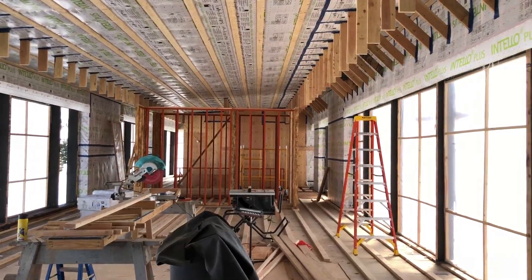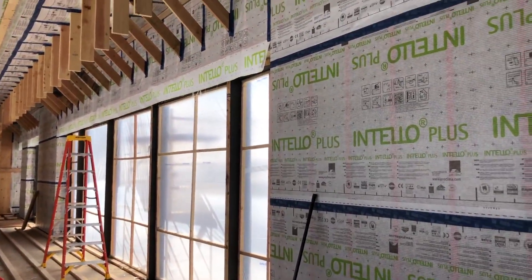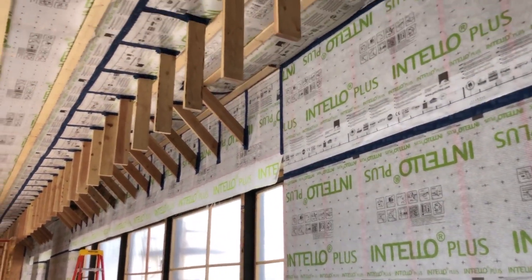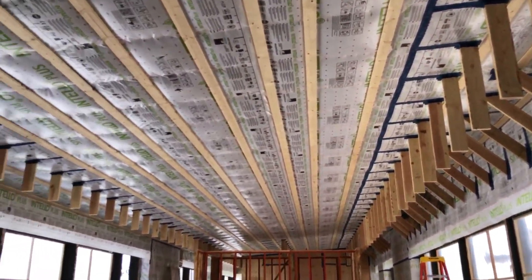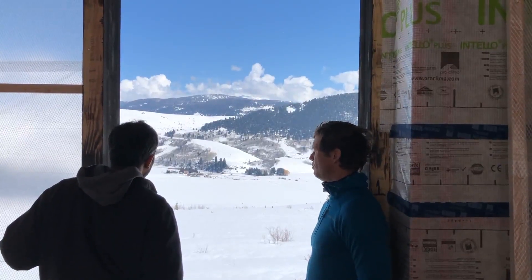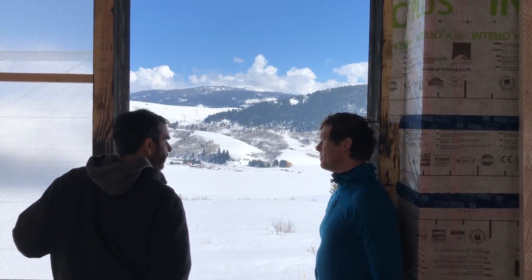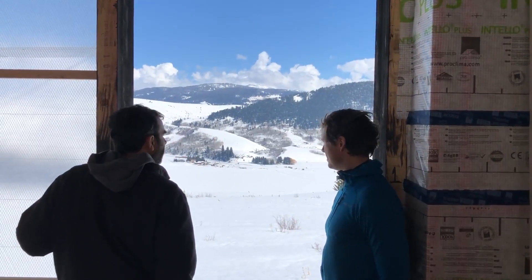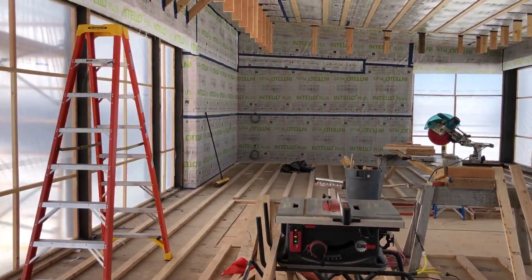The most difficult part of designing a building in such a cold climate is to provide suitable thermal protection to all components of the thermal envelope. Windows, doors, skylights — being holes in your building envelope — you do need to provide good enough quality for them. While code in this climate prescribes a 0.32 or 0.30 U-value window, here you're looking at 0.11 — a considerably higher performance in the transparent components compared to code windows.